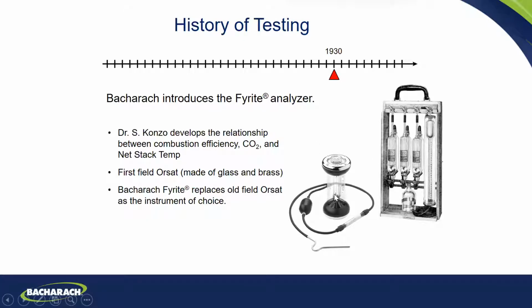It's an hourglass-shaped device called a Fyrite. It was a portable ORSAT you could take into a boiler room. You'd pump a sample out of the flue, pump it 20 times, then turn it upside down several times. It mixes with the fluid and gives you a direct concentration of either CO2 or, with another unit, oxygen.